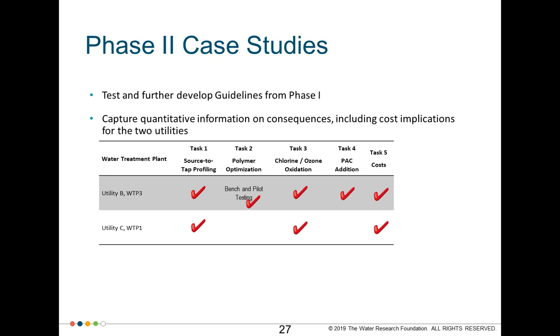In phase two, we tested and further developed the guidelines from phase one. One objective was to capture quantitative information on consequences, including developing cost opinions for two utilities — utility B and C — for implementing control strategies and mitigating unintended consequences. We conducted four quarterly source-to-tap profiling events and two rounds of bench testing of different control strategies, two rounds to capture performance under different seasonal conditions.